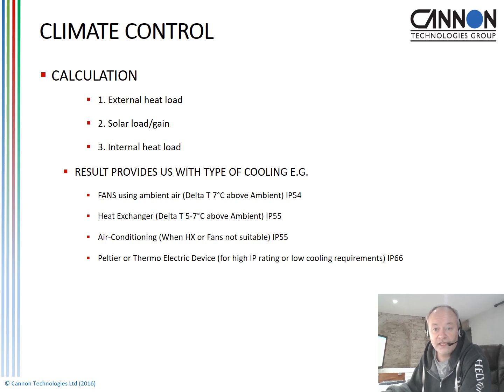That equipment is going to produce heat, as I mentioned, internal heat load, so it needs to be cooled in some way, and we would need to use an air conditioning unit in that instance. Other options, if we want higher IP ratings, are Peltier devices, thermoelectric cooling devices, which are pretty inefficient but obviously provide that higher IP rating.